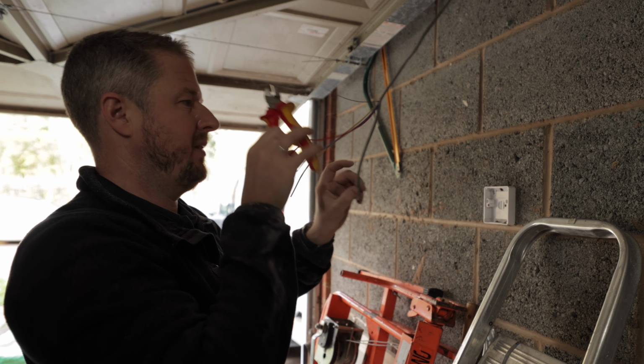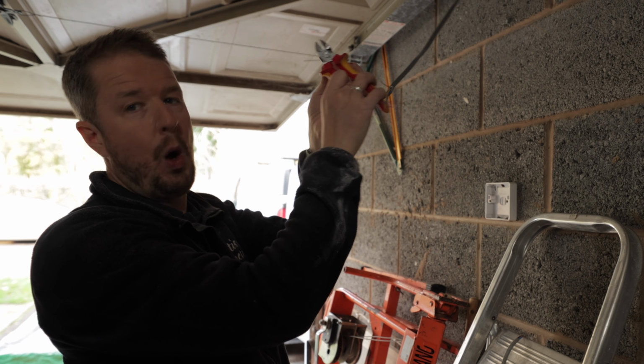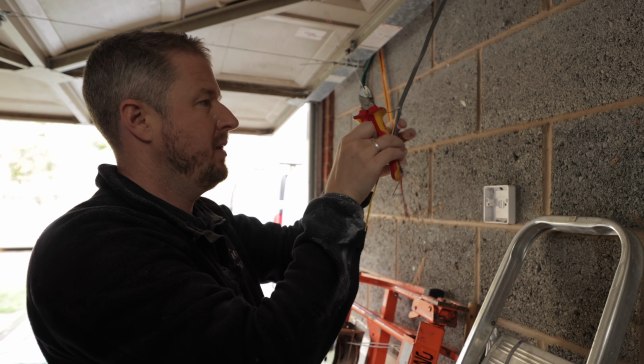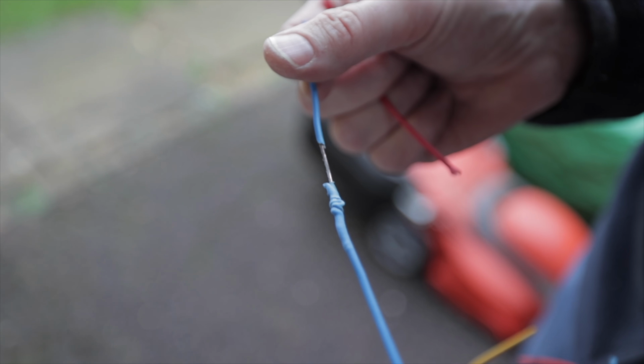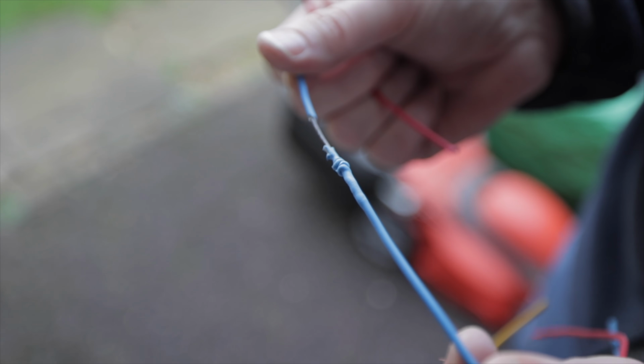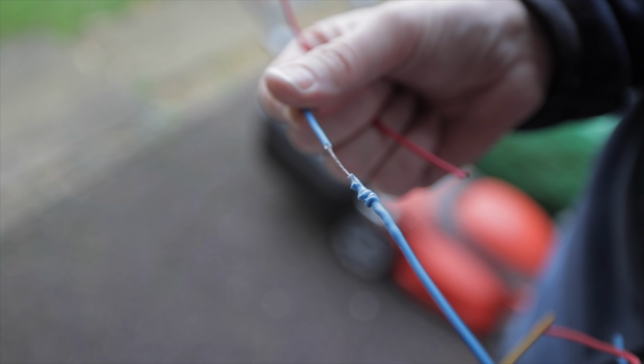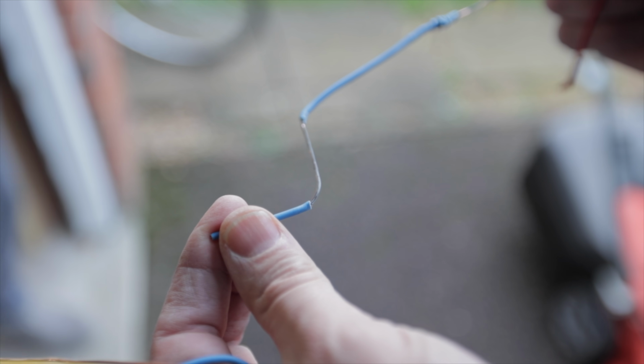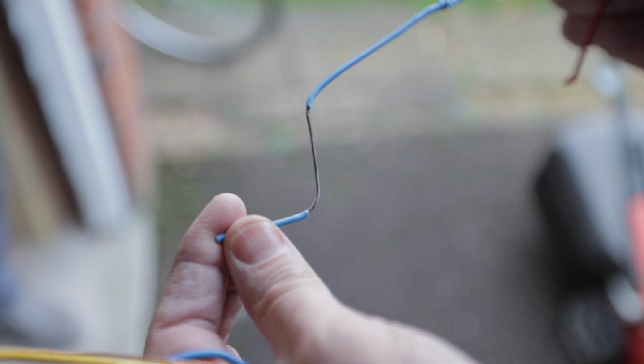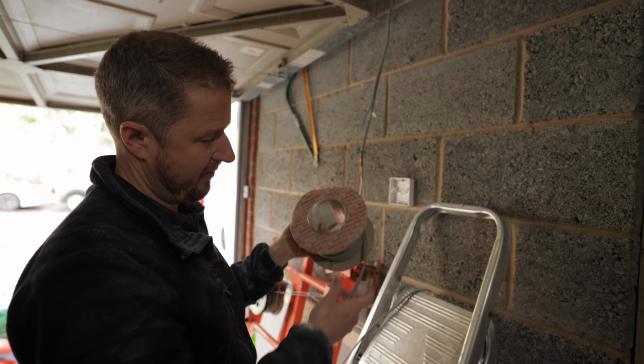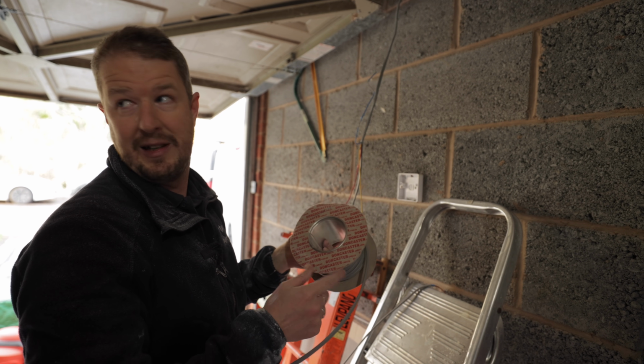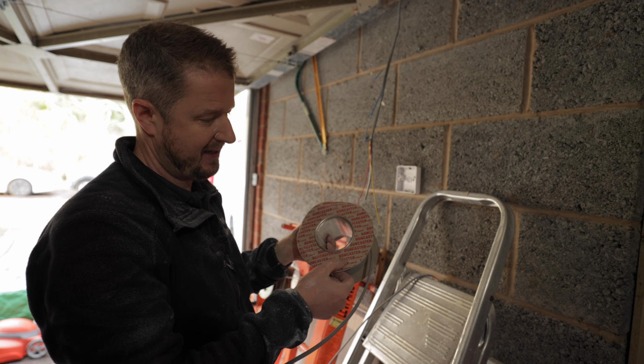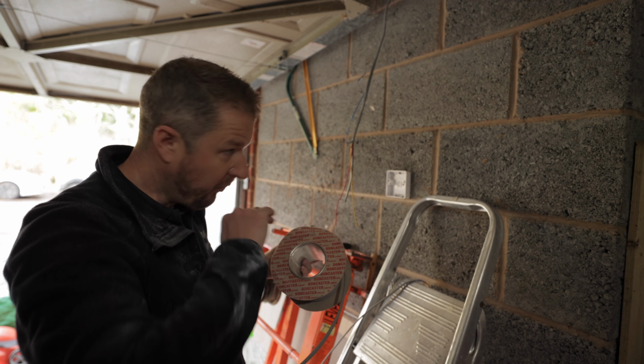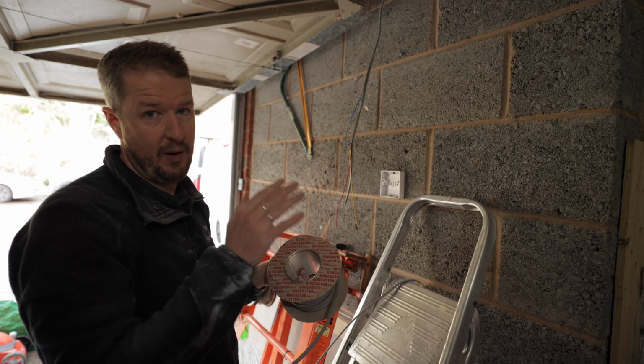And potentially what's happened is the whole insulation of the cable has actually become live. Yeah, look at that, it's the cable. The entire cable is all black. The insulation of the wires has failed. I'm going to give a free shout out to Doncaster Cables here, right? Because our friend Hacker, he's got good taste in cables. He uses good quality stuff for his customers. Doncaster Cables, amazing quality. We only use them.